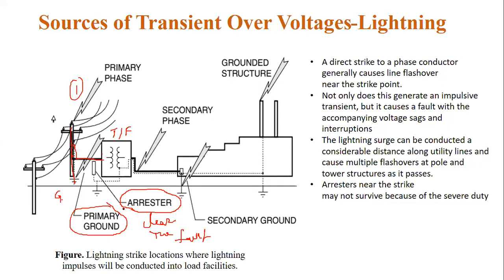Will not clear the fault 100%. Okay. So why is it not? Because before the clearing of the fault, through these arresters as well as the primary ground, some amount of voltage is injected into the primary of the transformer.